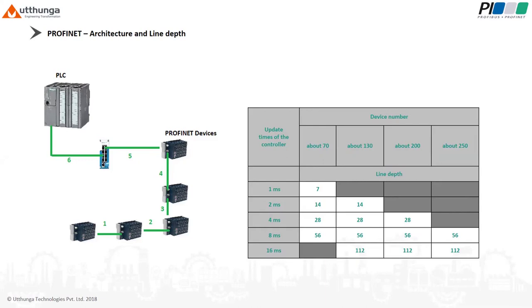But for a 1 millisecond cycle time, the maximum devices that can be connected is 70. Even if I'm stretching with switches, I should look at how many devices can be connected to the overall network. That depends upon the update time set in the controller. This is actually very important to design the PROFINET architecture, and also we can understand how to reduce the downtime and what is happening in the network or architecture.